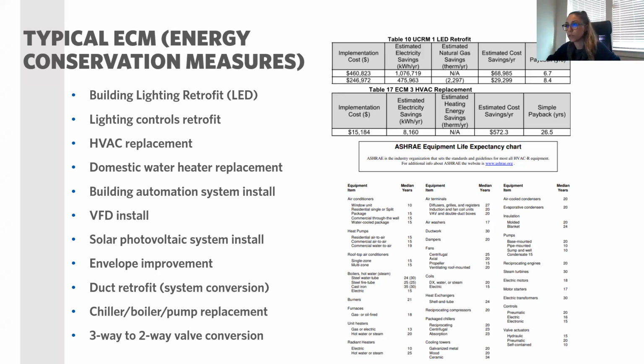And lighting controls with occupancy sensors, motion sensors, lighting sensors. There are different technologies available. And for HVAC replacement or water heater replacements, we typically use the ASHRAE equipment life expectancy chart. That helps us determine if the equipment is actually at the end of its life. So is it actually a good time to replace it? That typically also matches the operational problems that we are seeing. So if there's no damage, but the equipment has already ended its life, we typically recommend that replacement.